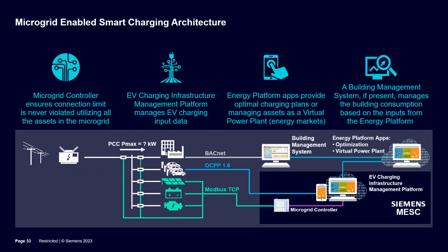That microgrid controller ties right into the EV charging infrastructure management platform, which manages the EV charging so we don't create a peak demand that exceeds the physical limitation. There are capabilities through that platform to optimize charging against on-site generation, including battery storage, which can be dispatched as part of the peak shaving process. If there's a building management system in place, that can also be part of the ecosystem the microgrid controller manages.